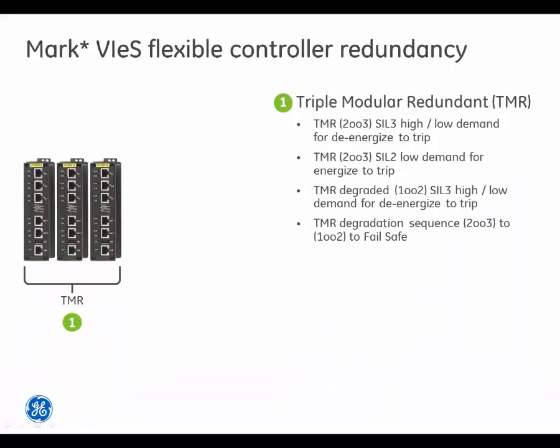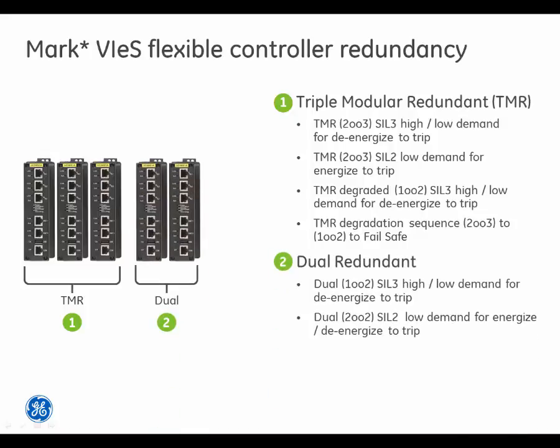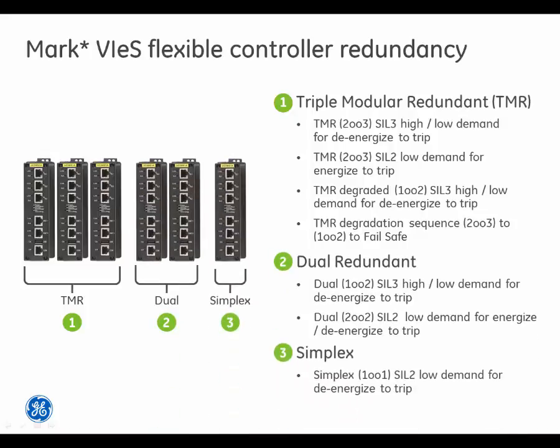Mark VIeS Flexible Controller Redundancy options include triple modular redundant (TMR), dual redundant, or simplex. Simplex, dual, or triple redundant I/O networks and processors can be mixed and matched over the Ethernet backbone depending upon SIL and redundancy requirements. I/O can be distributed locally or remotely, and you only need to install and maintain the level of redundancy required.